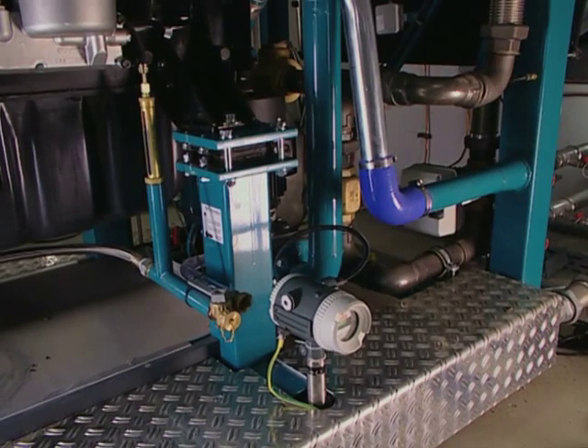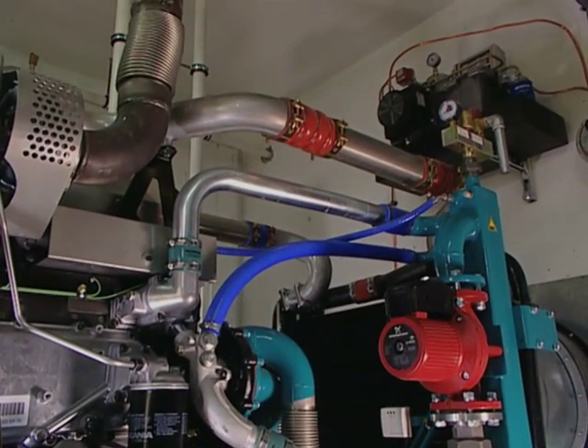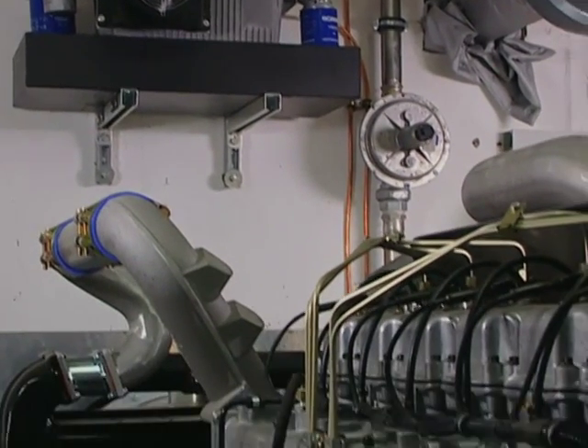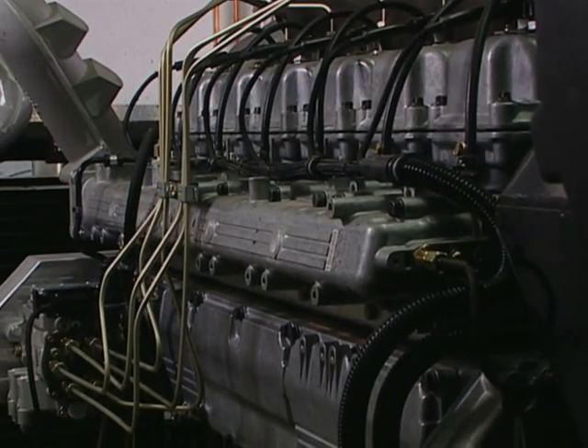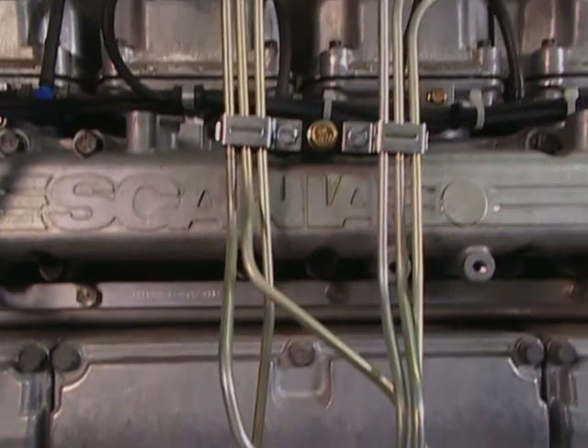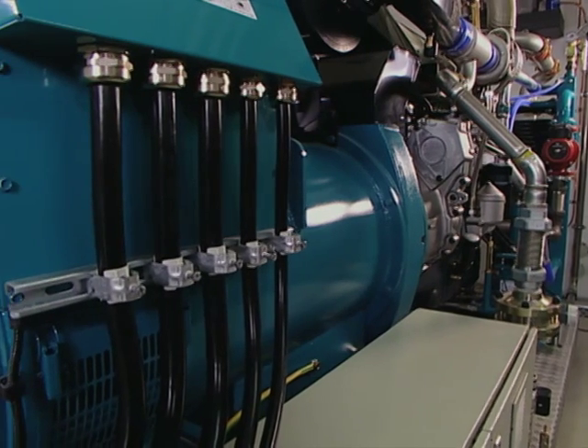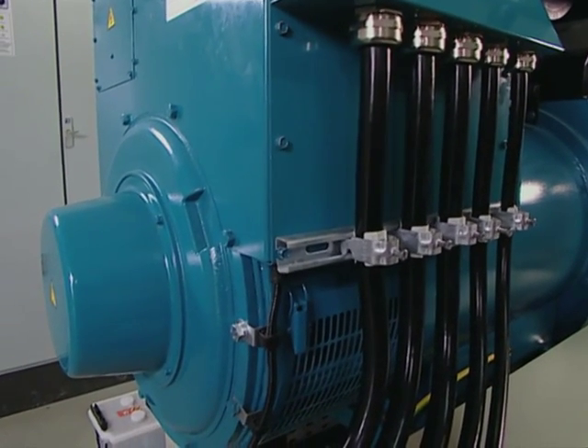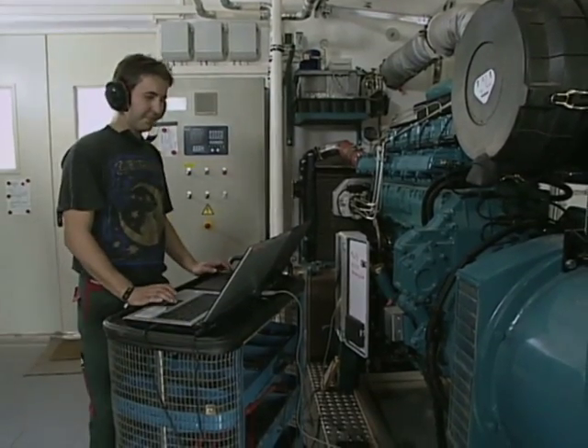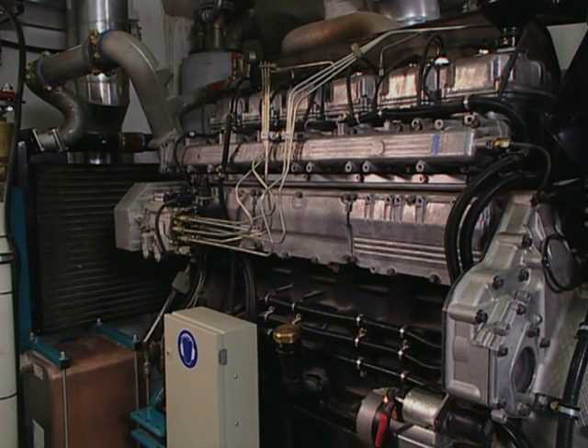Agri-Comp has chosen an incredibly efficient series of engines rated up to 45.5% electrical efficiency. These engines are turbocharged and incorporate state-of-the-art blue rail technology. With blue rail, a small proportion of the biogas is ignited in a specially developed pre-chamber, producing a jet flame that ignites the gas-air mixture in the standard combustion chamber and provides far more efficient power generation. The biogas plant is monitored and maintained via a control board which regulates all aspects of plant operation and alerts the operator of any changes that need to be made.